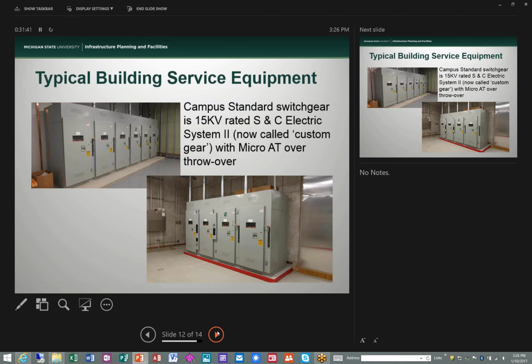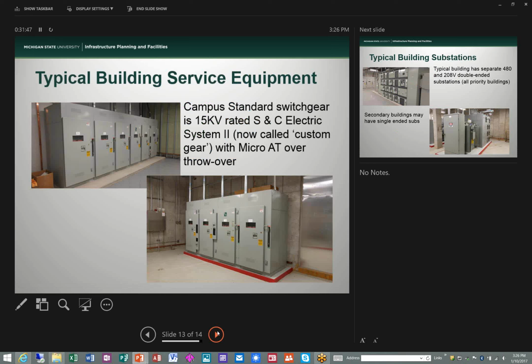The typical building service equipment, as noted, serves each building at 13.8 kV, using S&C's System 2, the old System 2 gear, now called custom gear with micro AT throw-over control. We've got double-ended subs in most of the buildings. What you see in the lower right corner is a building with two single-ended subs, in the vault outside the IM Circle Sports complex.